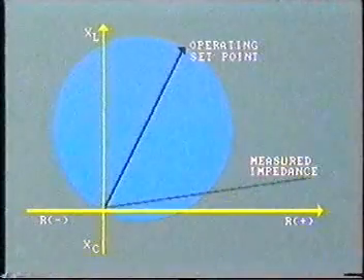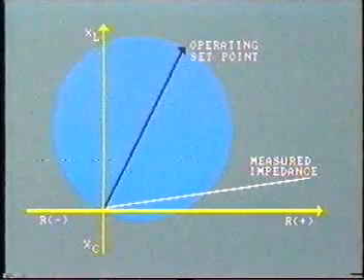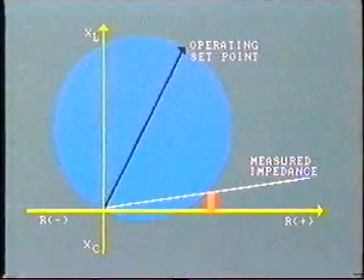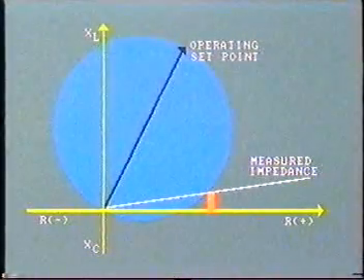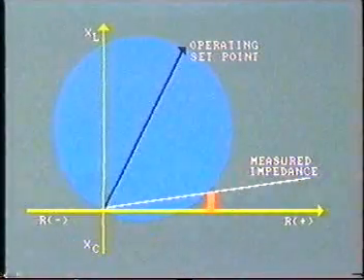It also increases the magnitude of the impedance. Consequently, even if the fault is only halfway along the line, the measured impedance often falls outside the operating circle.